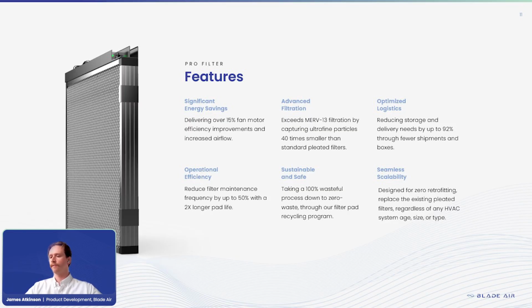Instead of just relying on a passive mesh or a pleated filter like a HEPA or almost like a coffee filter. The more dense your weave, the better filtration you get, but also the harder it is to push air through it. So because we don't load as fast, because we have that coarser mesh, you can actually increase your duty cycle as well. So you reduce your maintenance, right? We can double the lifespan of a typical pleated filter, and it produces much less waste.